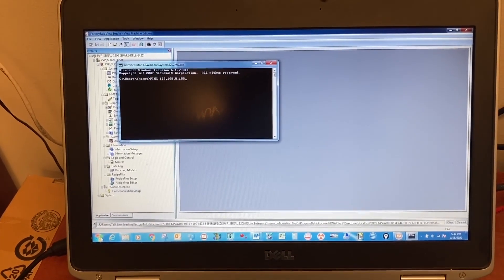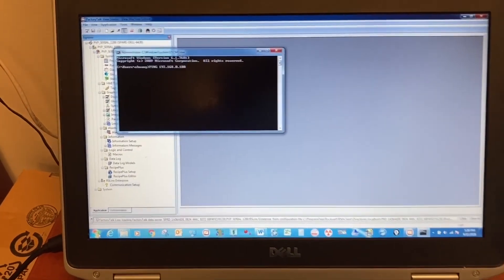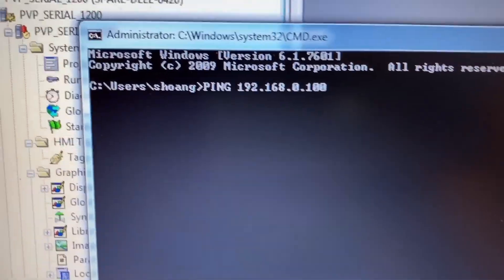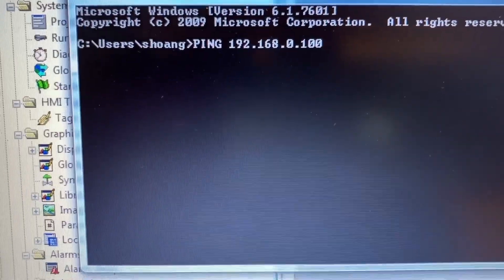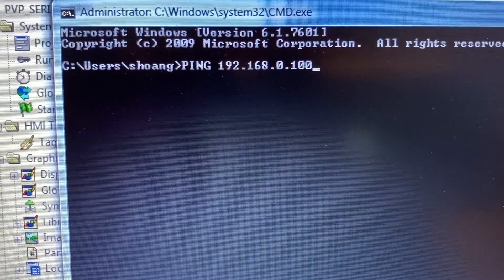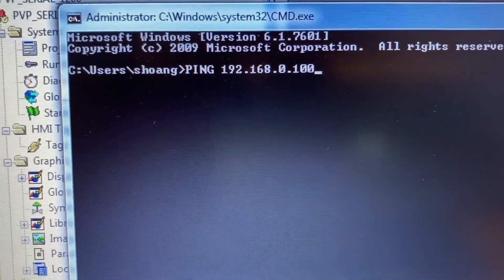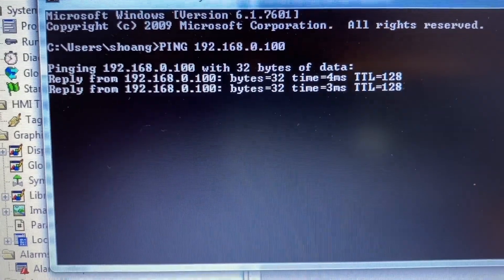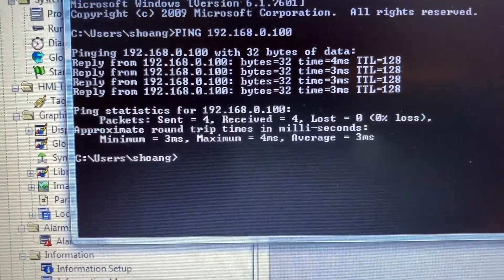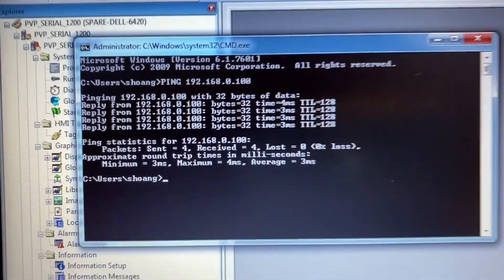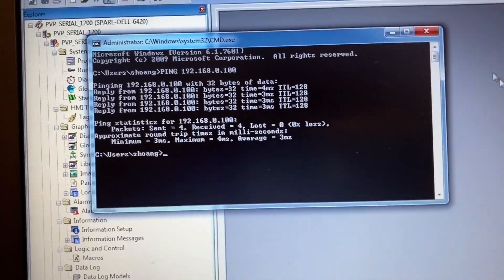Back on the computer, after connecting the HMI to the computer, make sure the connection between the HMI and computer is good. The HMI IP address is 192.168.0.100 — ping shows 0% loss, so connection is good. Close.